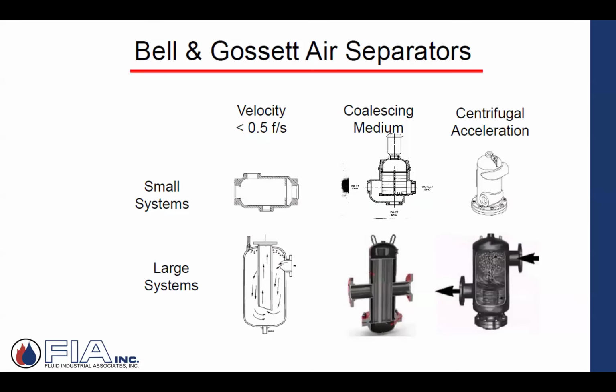So we're going to have some type of air separator. This simple screen is just saying, hey, there are different technologies. Velocity is a method that they use to separate air from water. Coalescing medium is another method. And then centrifugal acceleration is the third. These are pretty standard, accepted technologies that are used. And then you'll see small or large, as you get into residential sizes, or you get into the commercial with these Rolairtrol or these larger coalescing air separators.